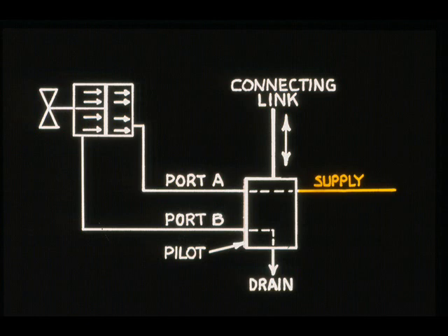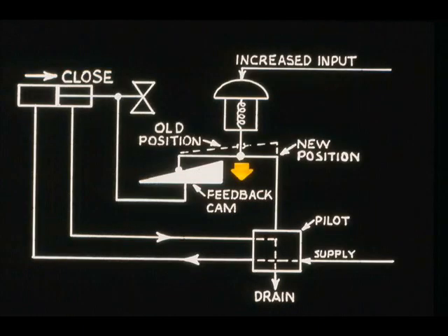To open the valve, port B is connected to the supply and port A is connected to the drain. To close the valve, port A is connected to supply and port B is connected to the drain. So by increasing the input signal, we move the pilot and close the valve.